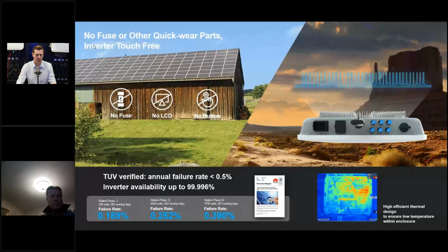be replaced every few months, or maybe a few years, sometimes even after a few months, because of usage of those parts. Also, up to 60 kilowatt inverters, we have only passive cooling in our inverters, so there is only a very small fan inside the inverter, not actually sucking or putting out the air, just inside the inverter to mix the heat inside the inverter. So this is how it was developed by Huawei.